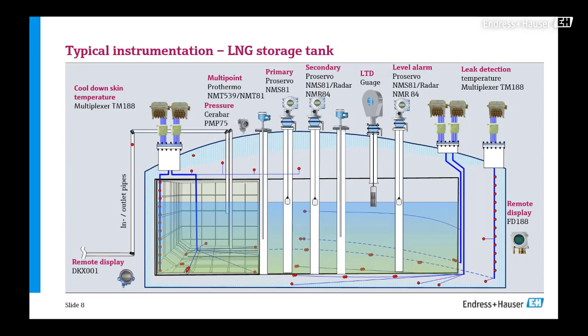Then the next one is what we call a pressure gauge. The pressure gauge is used to monitor the pressure inside the tank, especially if you have monitoring for the BOG. This is also typically connected to your ESD system. So here you can see a typical, very common instrumentation in a storage tank. And as I mentioned earlier, our high recommendation is of course to use a servo gauge because of some of the advantages that you can get with this technology.